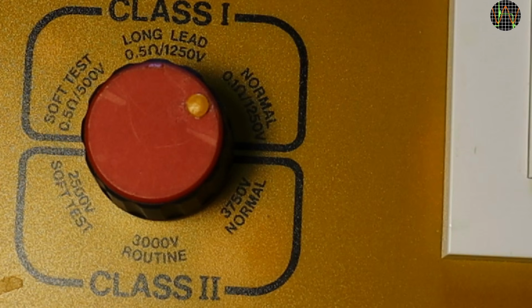However, let's pause a moment and examine the writing. Class 1 soft test uses 500 volts for an insulation test. That's what modern PAT testers use as well. But the other two class 1 settings use 1250 volts. That's more than double what modern testers do. And there are 2 numbers on each class 1 position, an ohm value and a voltage. This means this tester does 2 tests, testing how good the earth connection is in terms of its resistance, and a high voltage insulation test.